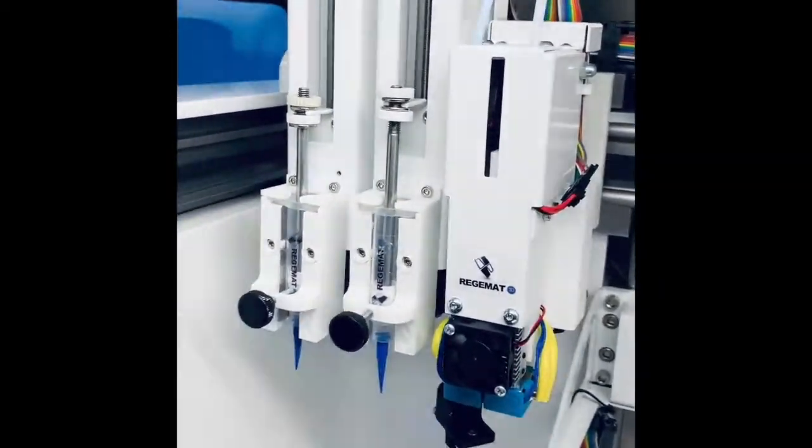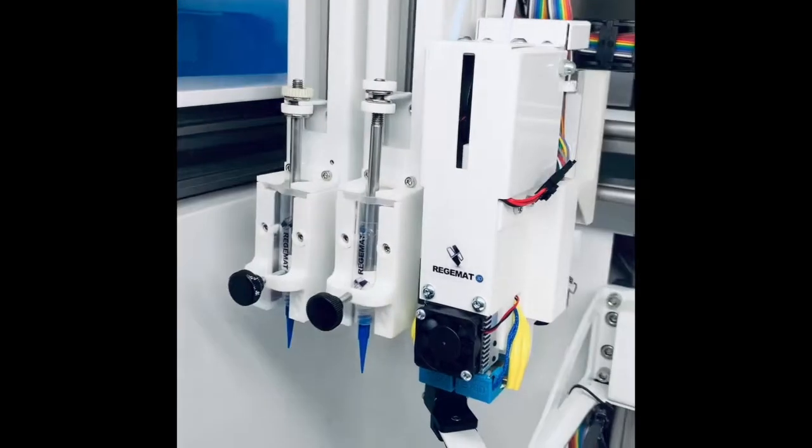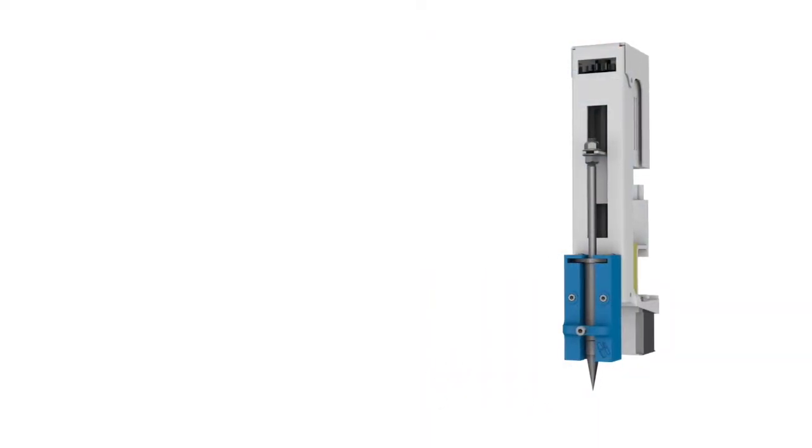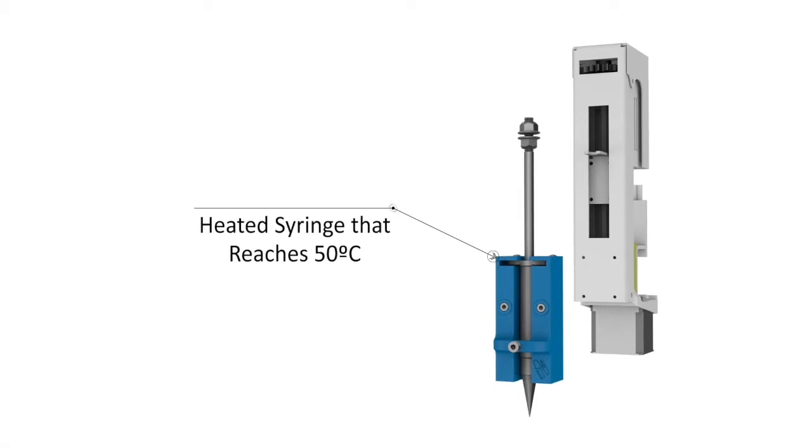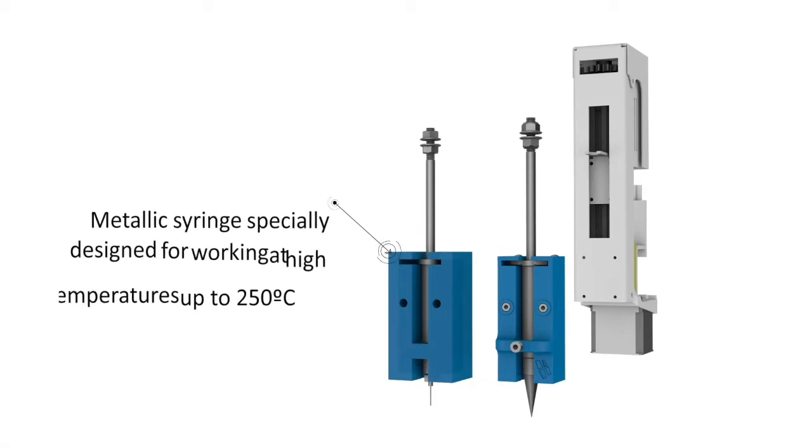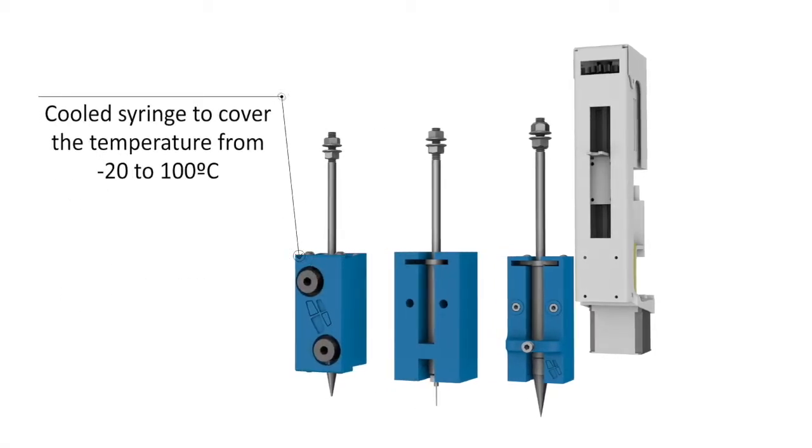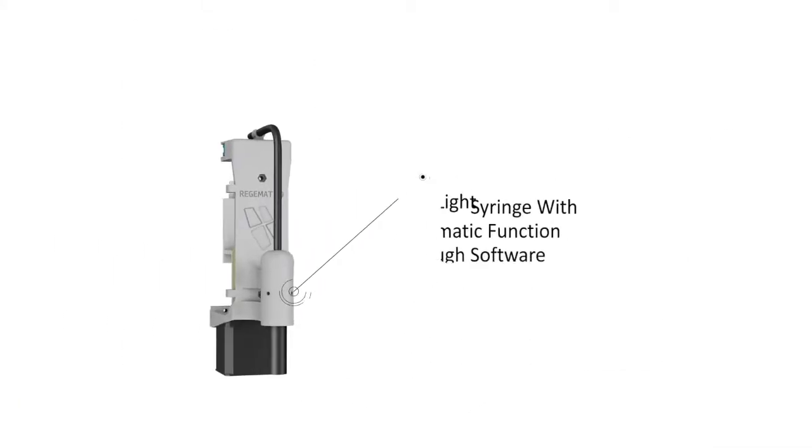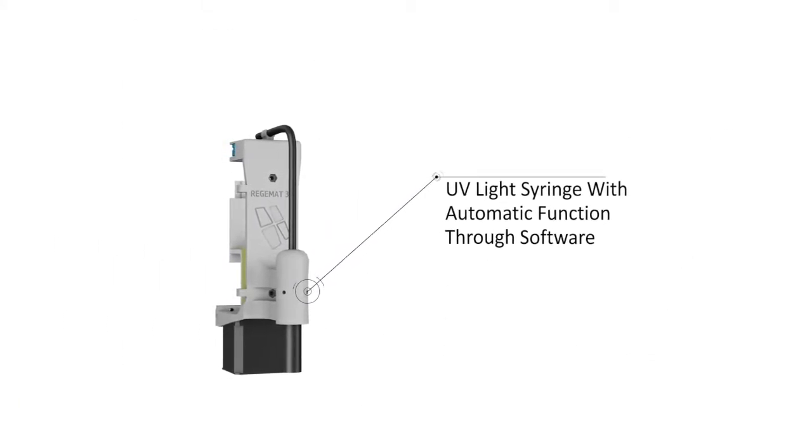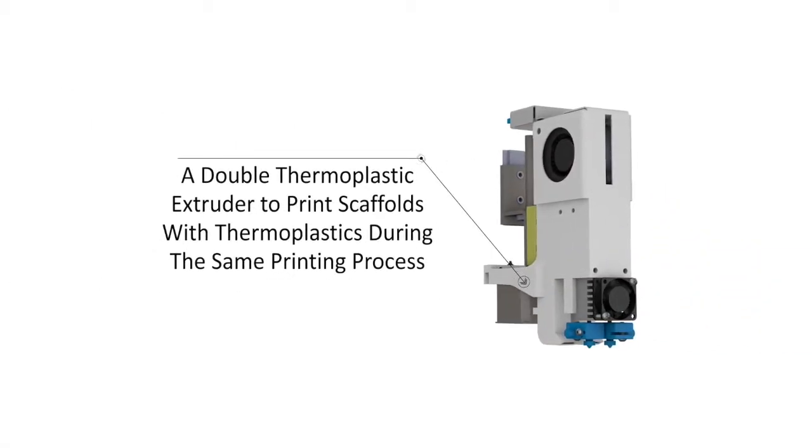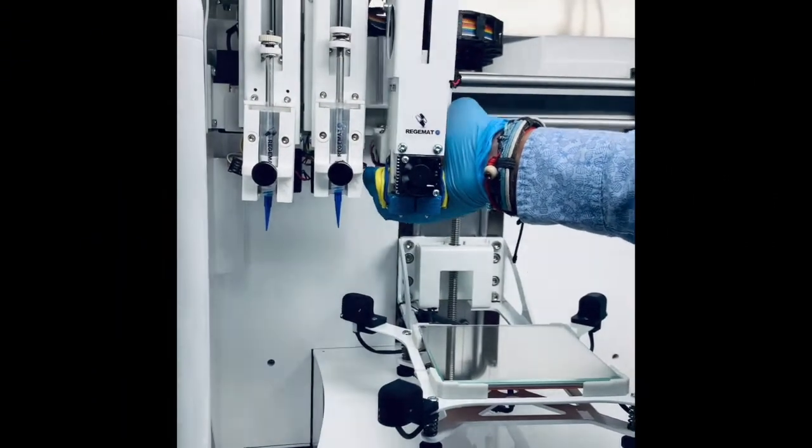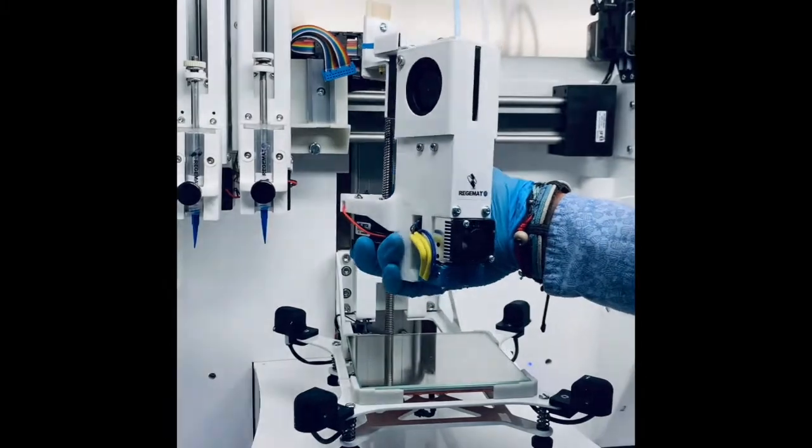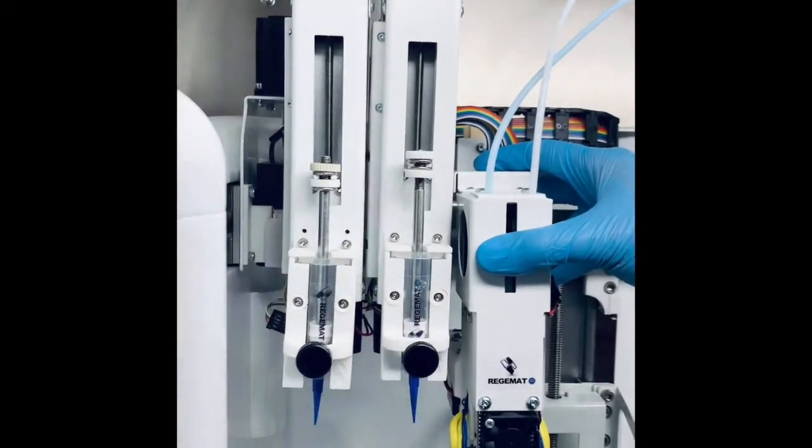You can fully personalize the printhead configuration with a wide range of advanced tools including a heated syringe that comes with the standard configuration, an ultra-high temperature metallic syringe and cool components for ensuring low temperatures in the whole extrusion system. You can also include a UV light for polymerization and cross-linking of hydrogels, and a double thermoplastic extruder system to create complex constructs. To facilitate the versatility of configurations, we have integrated a plug-and-play system to easily exchange tools in a fast and convenient manner.